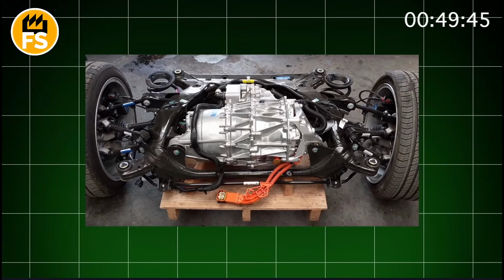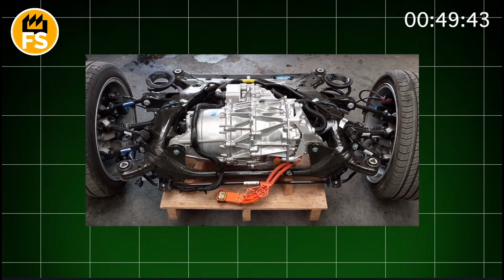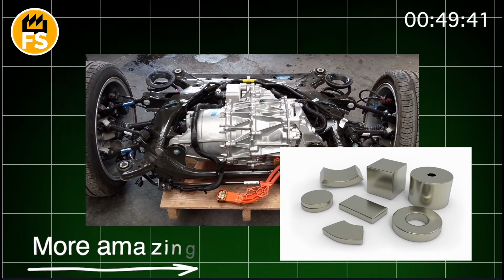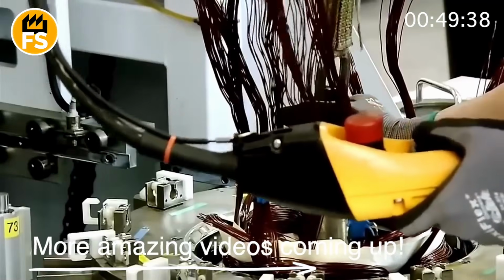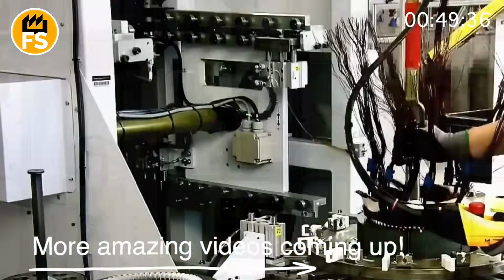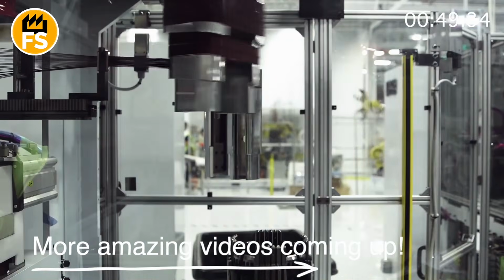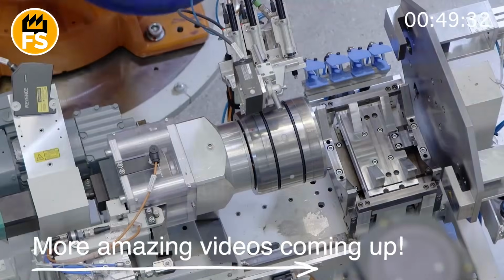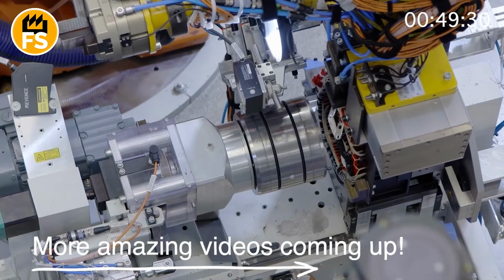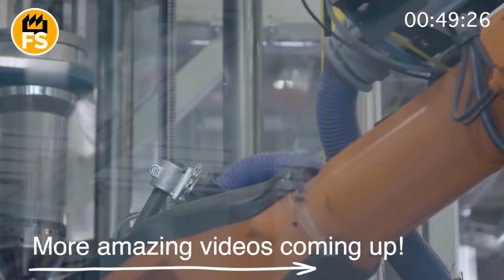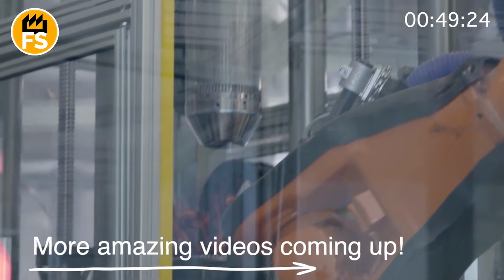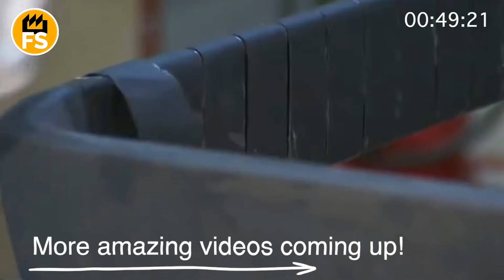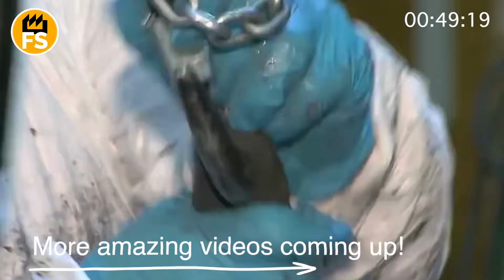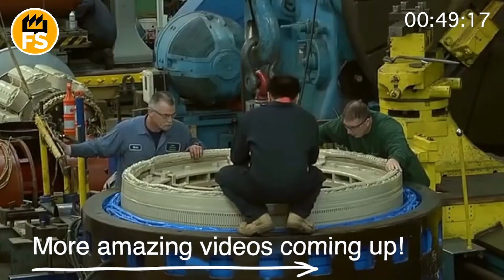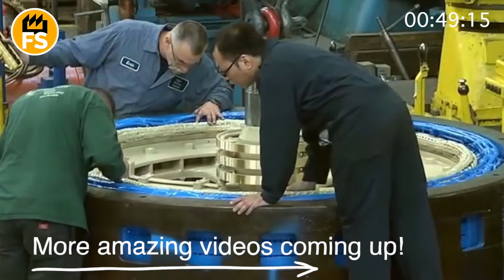After varnishing, the most sensitive stage, the motor is installed on a balancing stand. The system is like a huge record player. The motor rotates at high speed, and sensors detect the slightest deviations. Even a few grams of excess mass on the rotor can cause vibration that will destroy the bearings, shorten the service life significantly, or even ruin the motor. To eliminate the imbalance, engineers drill microscopic holes in the heavier part of the rotor, removing excess metal. This is almost a jeweler's craft.